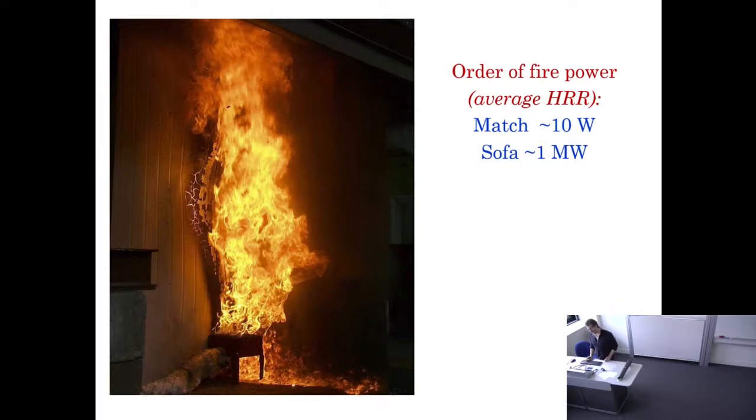When a sofa fire is burning, and that's more serious, especially in residential locations, they might actually start burning because of a match. That happens very often, or a lighter, or a short circuit. But actually the average heat release rate, not even the peak, is about 1 megawatt. That's a serious change, right? This is 100,000, well, it's 10 to the 5 bigger than the match.